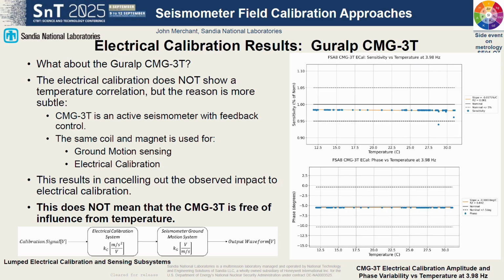Remember that STS 2.5 plot I said? This is an active broadband seismometer, and we're running an electrical calibration by injecting current into the feedback coil that it's then using to correct and sense, and so we actually believe that it is canceling out the temperature effect when you run the calibration. It's not invariant of temperature, it's just hidden from you when you do this electrical calibration. So what this would mean in this instance is that you're running this periodic electrical calibration and you're not seeing the true performance of the instrument because it's varying with temperature, and yet this method of calibration isn't showing you what you think it's showing you. So we're not seeing the true performance of the instrument.